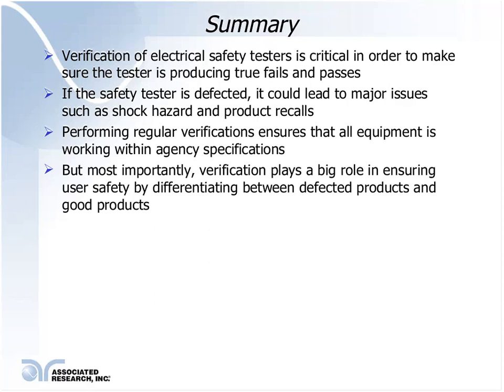At the same time, damage to such suppressors can cause false readings on an instrument. So, taking simple steps to run daily verifications can spare a great deal of trouble and effort down the road, and it can also help avoid costly redesigns or product recalls.